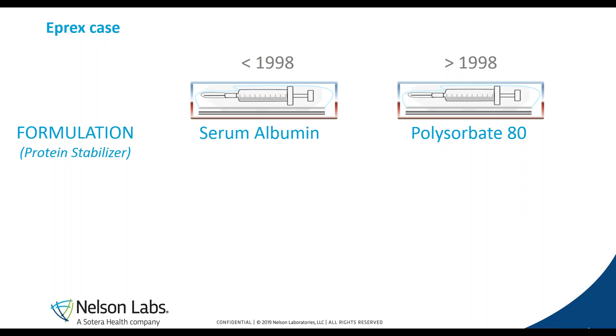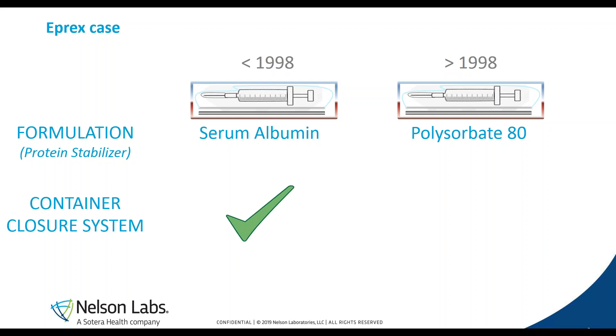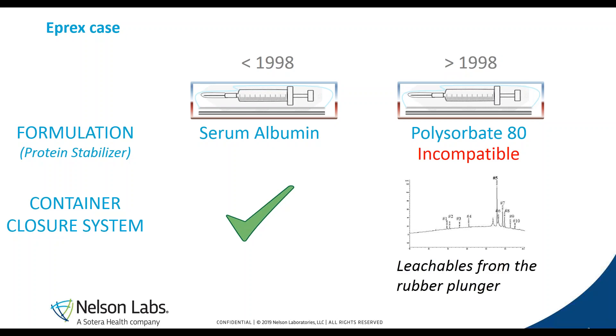Something very important here is that this formulation was contained in the same container closure system, in the same pre-filled syringe. So the materials in contact with this formulation were exactly the same using both formulations. The container closure system was compatible with the serum albumin formulation, but was found to be incompatible with the new polysorbate 80 formulation. A different leachable pattern was observed, and the leachables were found to be related to the rubber plunger present in this pre-filled syringe.